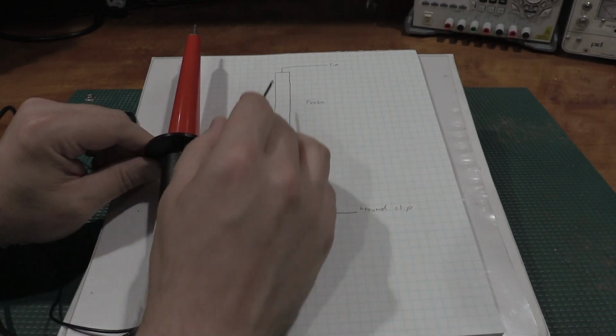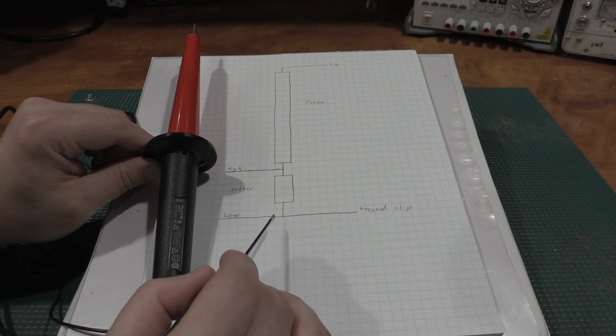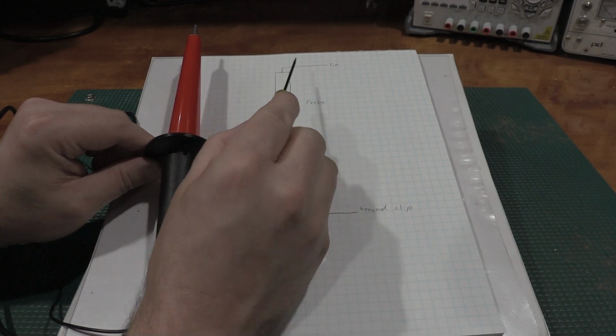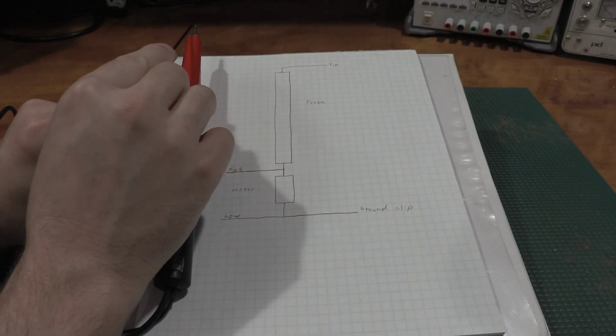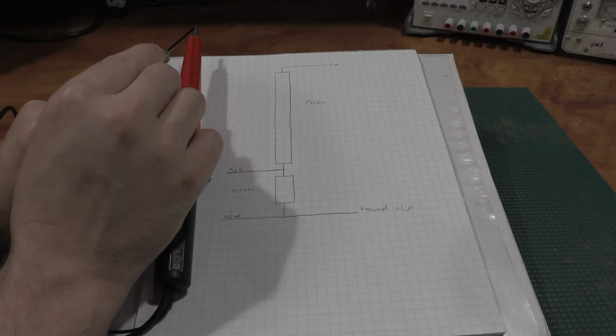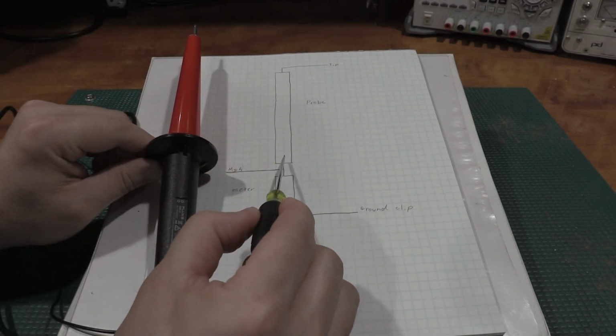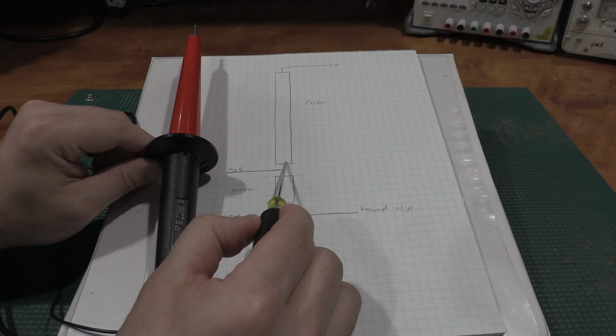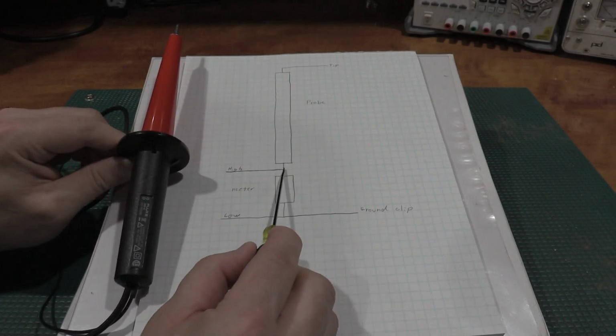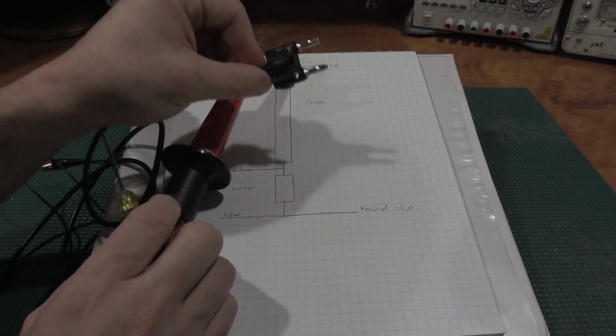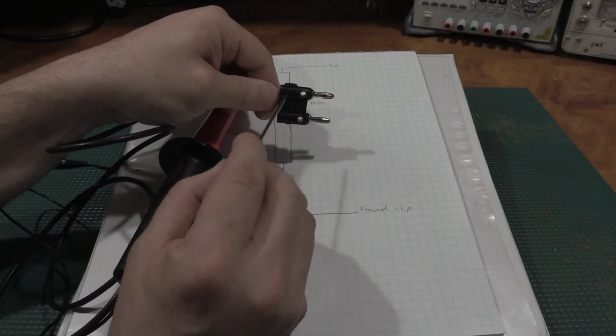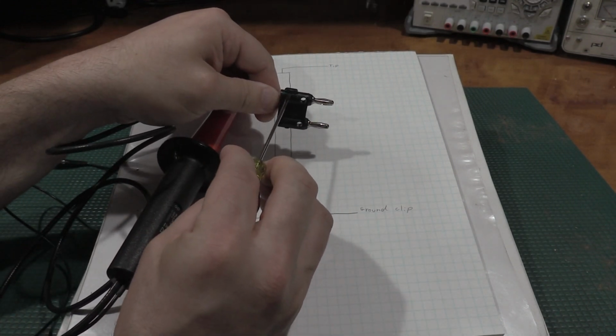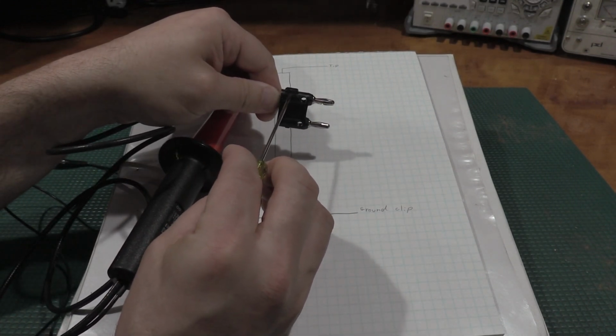Just something I had to get used to, but that's why it's drawn this way. The probe tip is up here, which is just the tip at the top of the probe. We go through the main voltage dropping resistor. Meter taps off here through this connector, and you'll note that right here, it says ground on the connector.